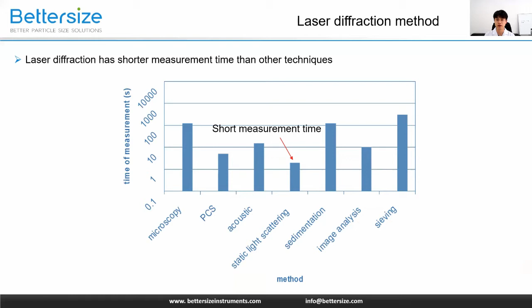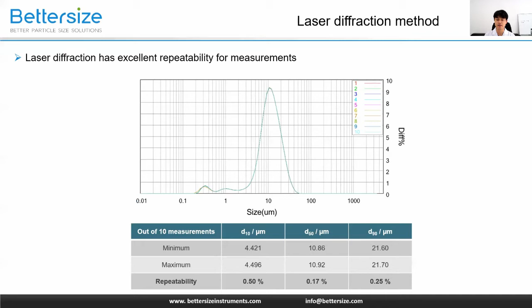And with correct operation, the measurement results of a laser analyzer will have excellent repeatability and reproducibility. In other words, there is a small relative standard deviation between each test result. The D10, D50, and D90 of the laser diffraction refer to the particle diameter when the cumulative distribution accounts for 10%, 50%, and 90% of the total content, respectively. Here, the repeatability of D50 is only 0.17%, which is actually far less than the ISO standard for laser diffraction.